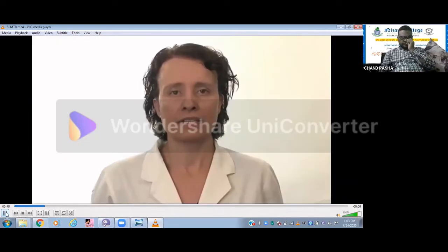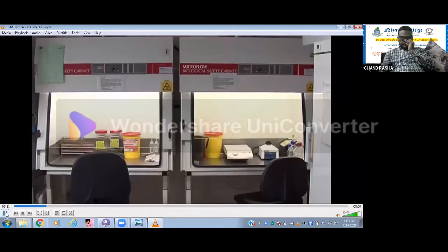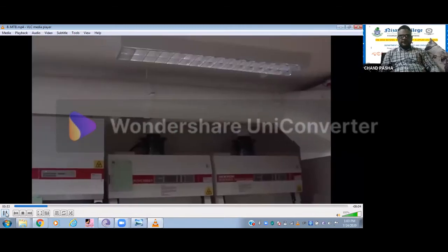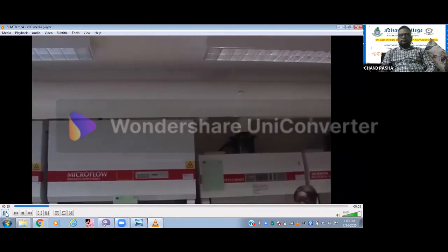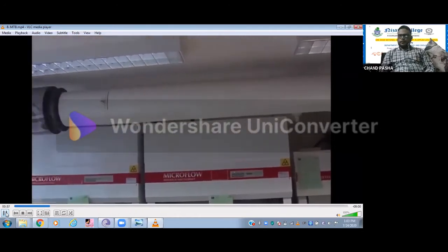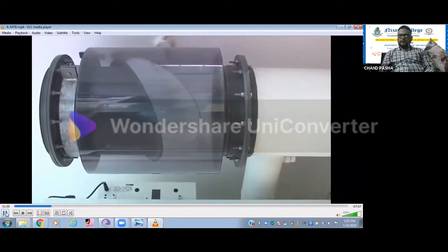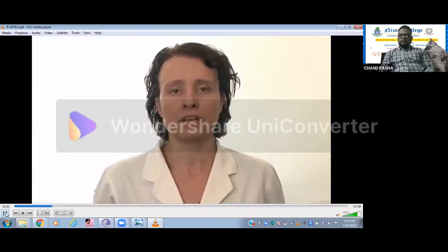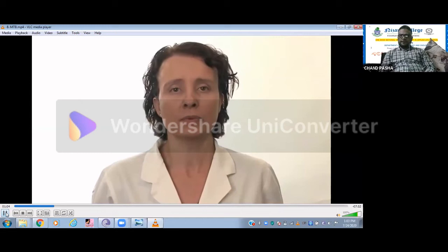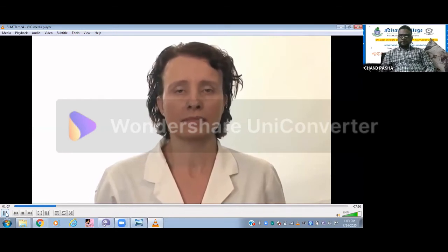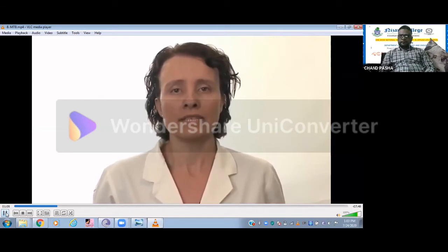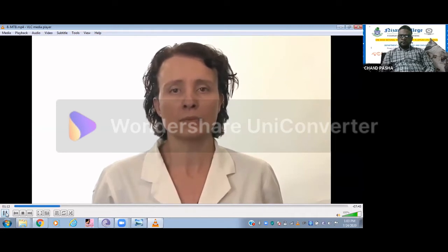The air extract system is provided by the Class 1 safety cabinets, through which airflow occurs via high-efficiency particulate absorption (HEPA) filters. The negative pressure in the room ensures that the airflow is continually pulled towards the cabinets and the HEPA filters. All investigations on samples within a Containment Level 3 laboratory are performed whilst working in the Class 1 safety cabinets.